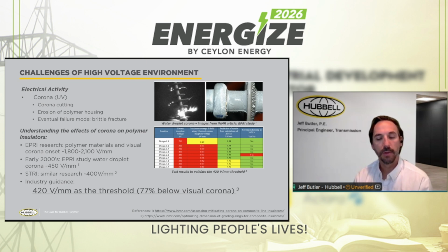It also emits a purplish bluish light, as well as an audible signature that sounds almost like cooking bacon or sizzling meat. So what was understood with further research from EPRI and STRI was that there were voltage gradients that perhaps were below what the threshold was for visual corona, what you would see out in the field on any given transmission line. And it was better understood that there were values below this that needed to be explored and understood. And this is done through simulation work in 3D modeling, coupled with laboratory testing.